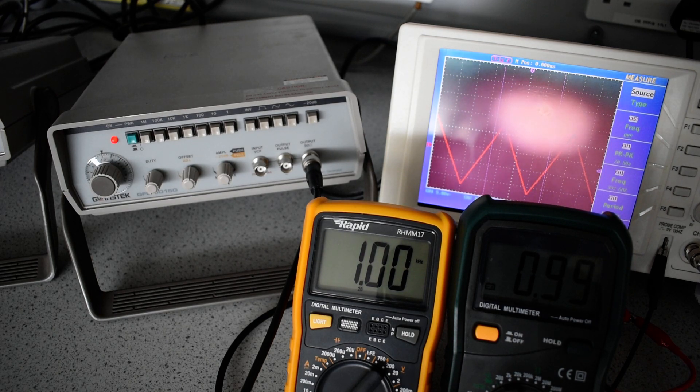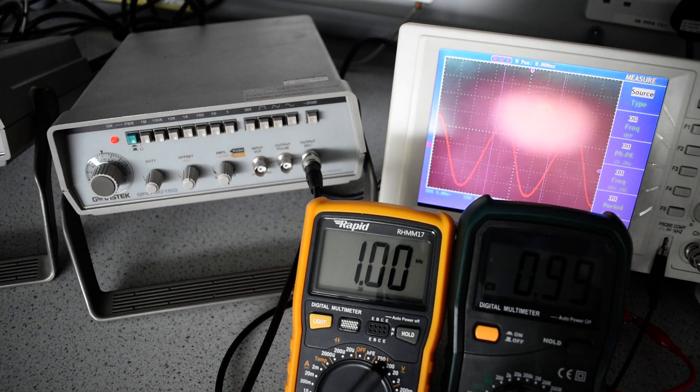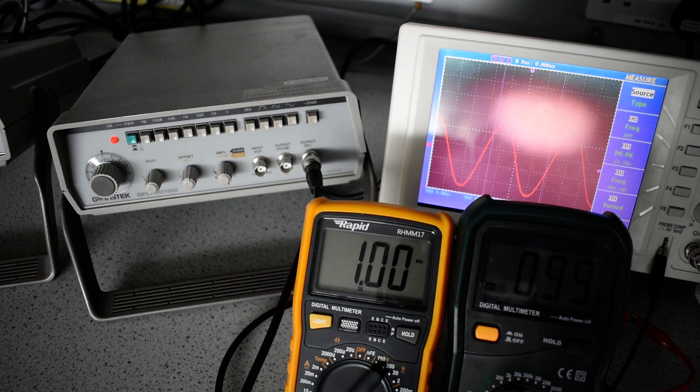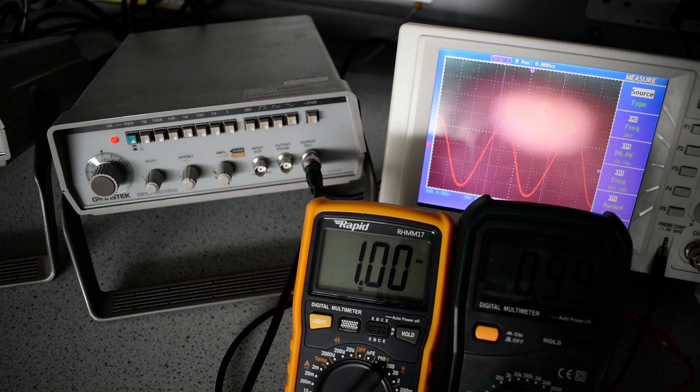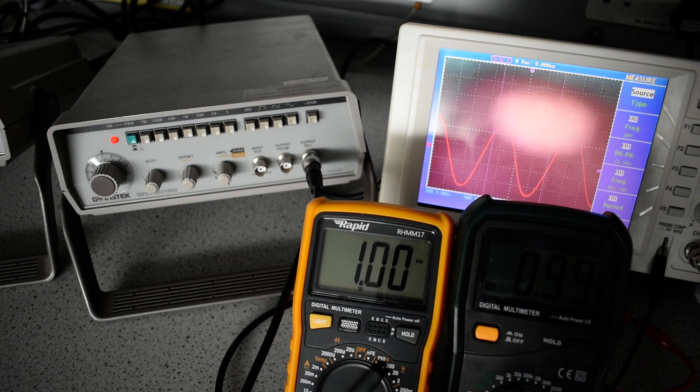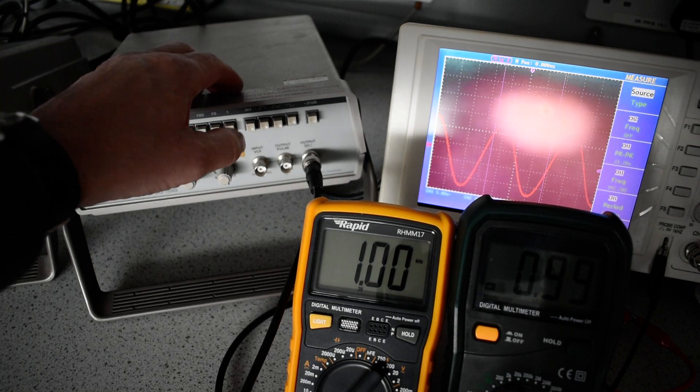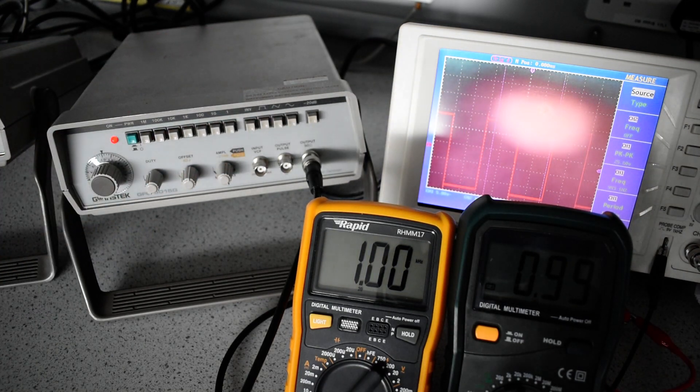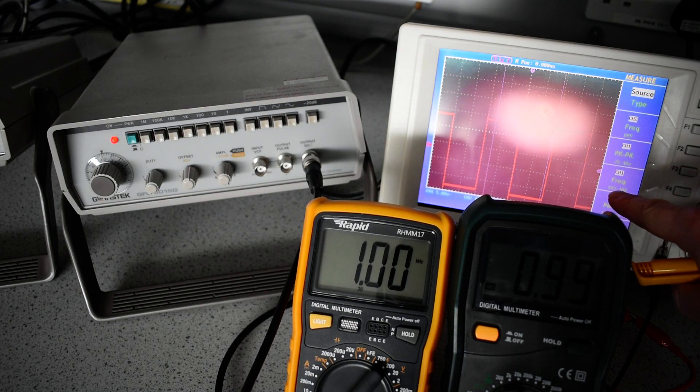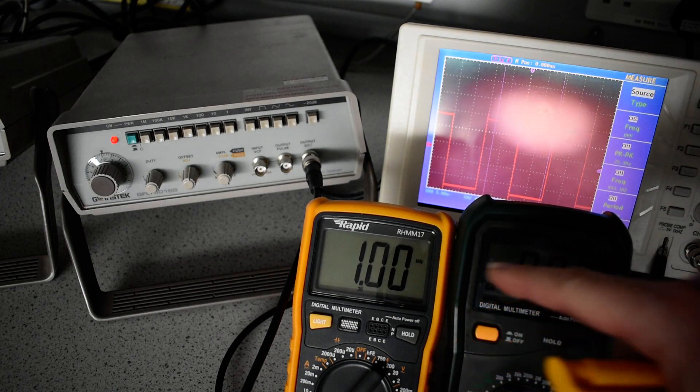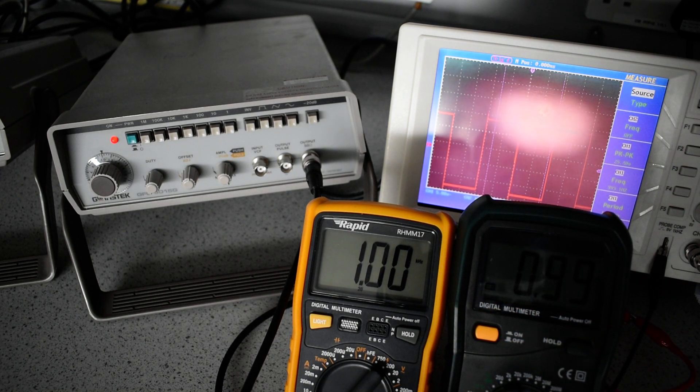So we are measuring within range. If we change it to a sine wave, then we still have a frequency of 993 on the DS25 and we've got the same frequencies on the digital multimeter, again within specified range. If we change it to a square wave, we have frequency measured 993 on our DS25 scope and again these frequencies are the same at 990 Hz.